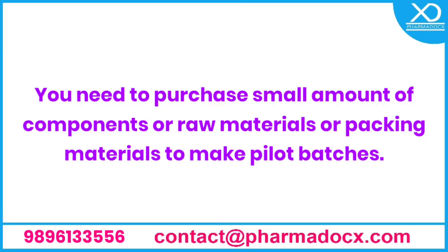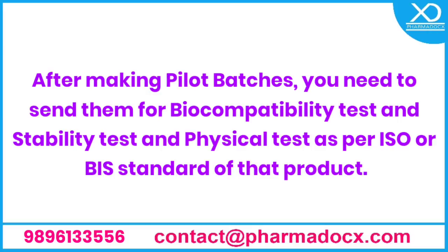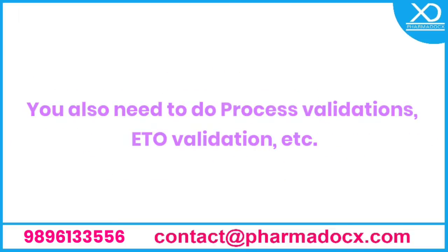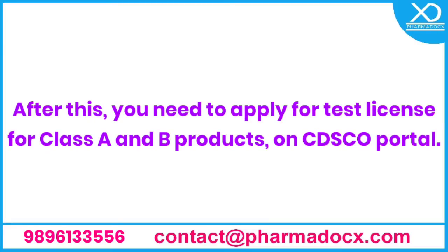After that, you need to purchase a small amount of components or raw materials and pouches and packing material so that you can make pilot batches. After making pilot batches, you need to send them to a biocompatibility testing laboratory, stability testing laboratory, and physical testing laboratory as per the ISO or BIS standard of that product. You also need to do process validations, ETO validation, etc. After completion of all these tests, you need to apply online on the CDSCO portal, first of all, for A and B class of products.